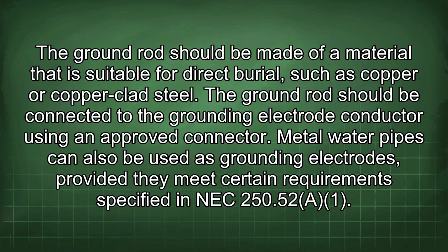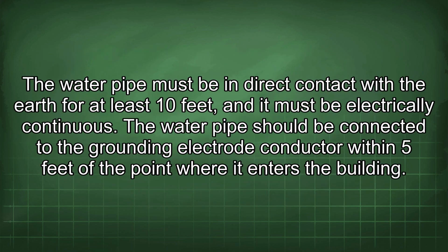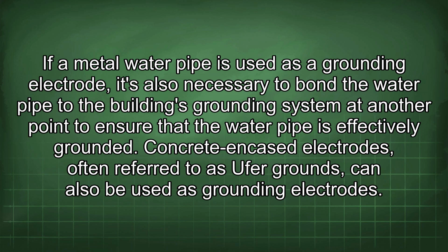Metal water pipes can also be used as grounding electrodes, provided they meet certain requirements specified in NEC 250.52(A)(1). The water pipe must be in direct contact with the earth for at least 10 feet, and it must be electrically continuous. The water pipe should be connected to the grounding electrode conductor within 5 feet of the point where it enters the building. If a metal water pipe is used as a grounding electrode, it's also necessary to bond the water pipe to the building's grounding system at another point to ensure that the water pipe is effectively grounded.